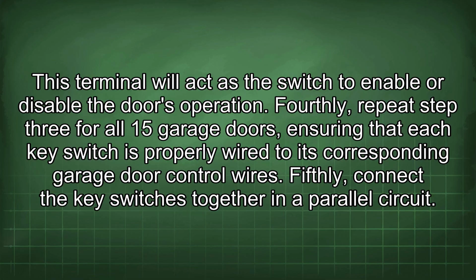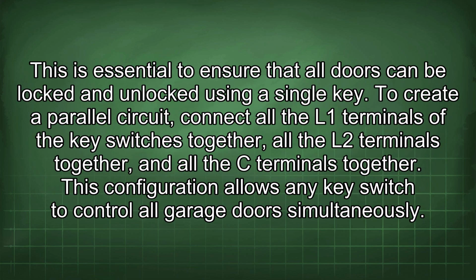Fourthly, repeat step 3 for all 15 garage doors, ensuring that each key switch is properly wired to its corresponding garage door control wires. Fifthly, connect the key switches together in a parallel circuit. This is essential to ensure that all doors can be locked and unlocked using a single key. To create a parallel circuit, connect all the L1 terminals of the key switches together, all the L2 terminals together, and all the C terminals together. This configuration allows any key switch to control all garage doors simultaneously.